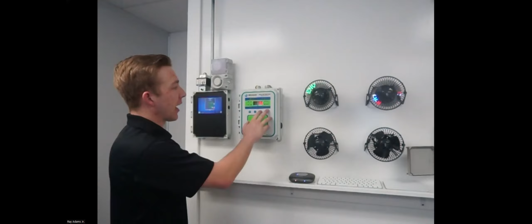And then, as I mentioned before, if those fans are not flushing the gas out to the capacity that they need, that's when your alarm would go off. There's an internal buzzer inside of the standalone, as well as anything else that you may tie into that alarm dry contact. Now, as I referenced, this is very simple and very straightforward. There's low alert, high alert, and alarm.